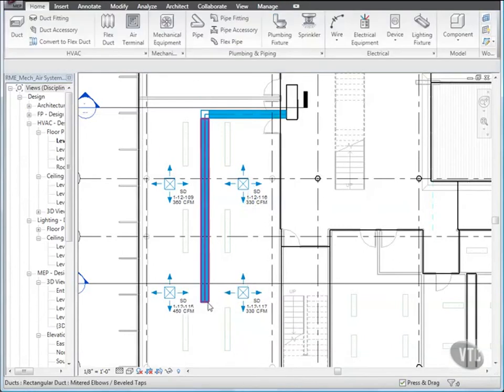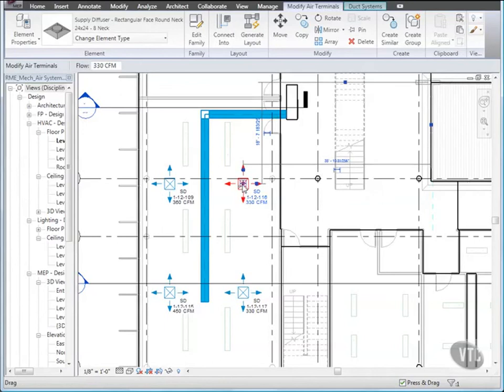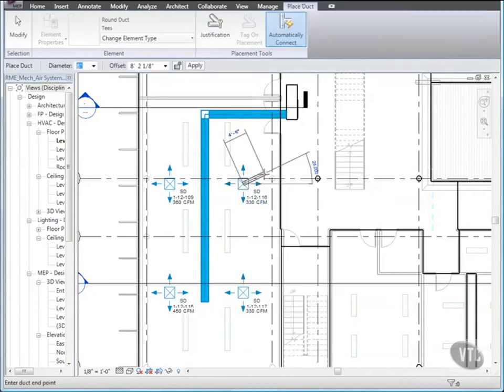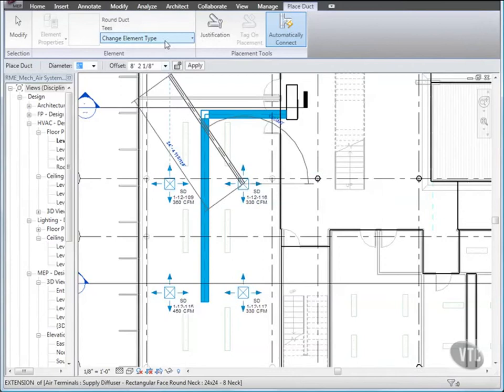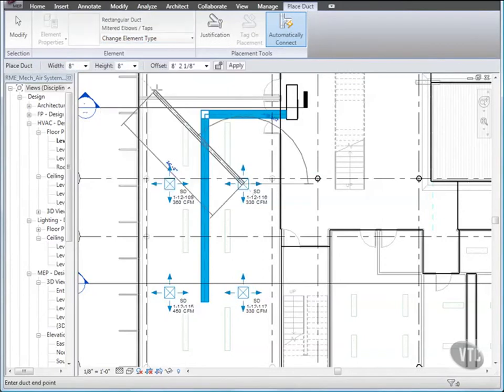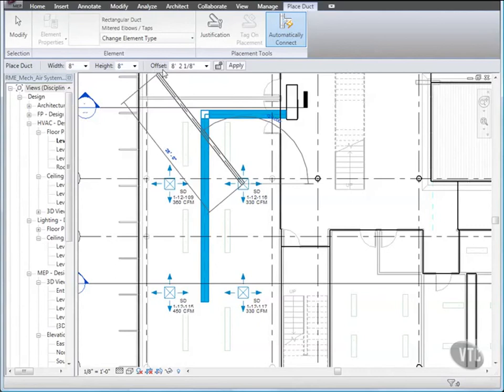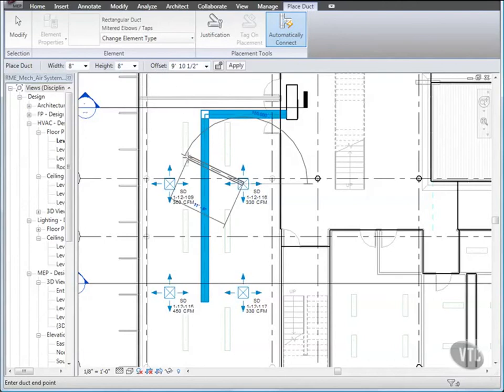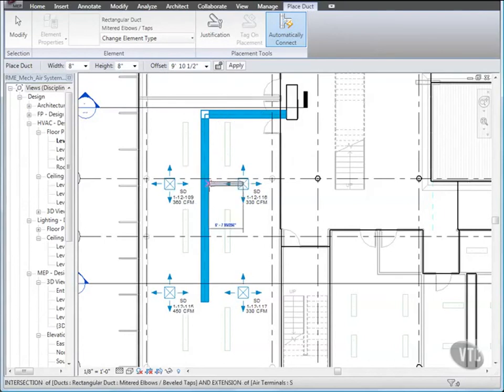To begin Branch Duct, select the top right diffuser, right-click the connector grip, and click Draw Duct. Then click Change Element Type and select Mitered Elbows and Taps. And on the Options bar, for Offset, select 9 feet 10.5 inches. Then click the intersection of the branch duct and the main duct. Then click Modify.